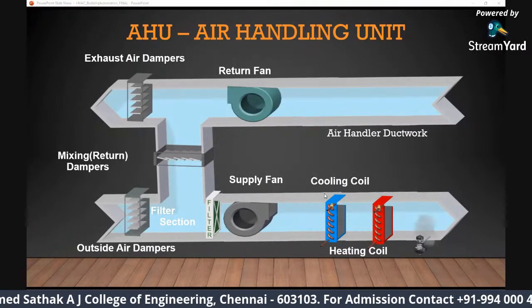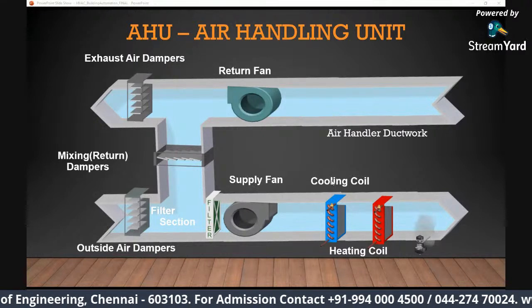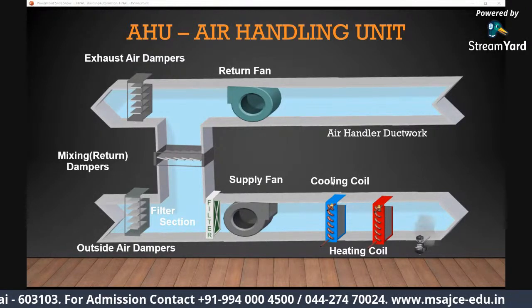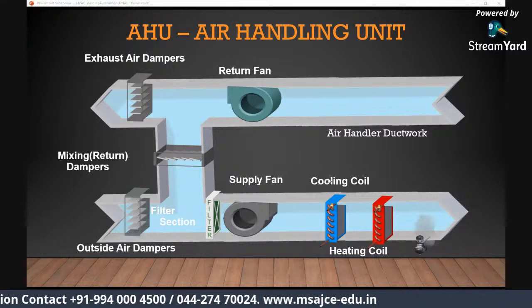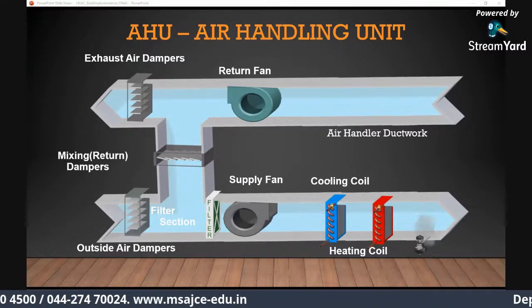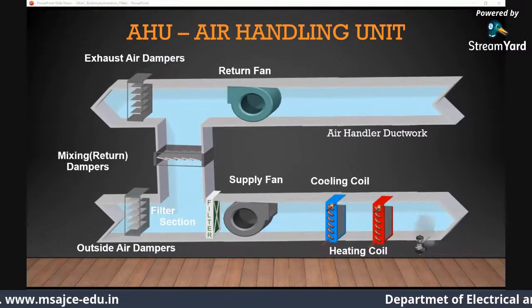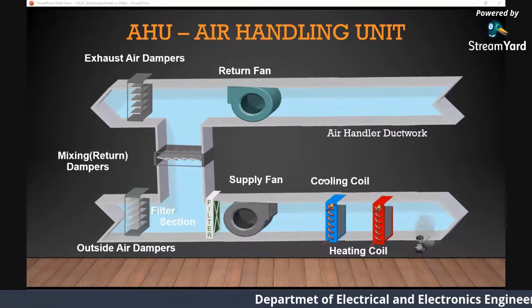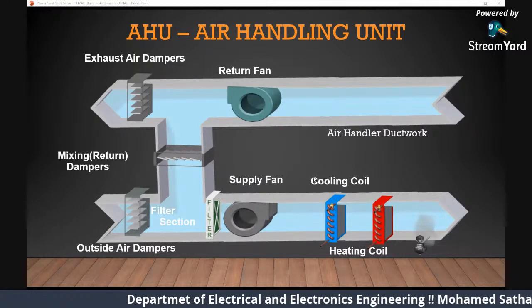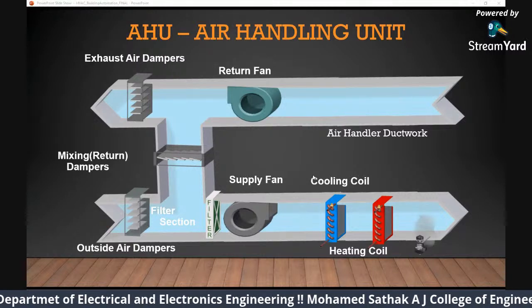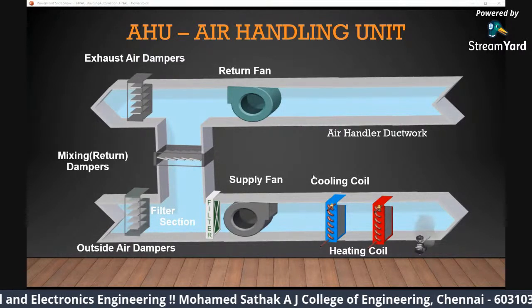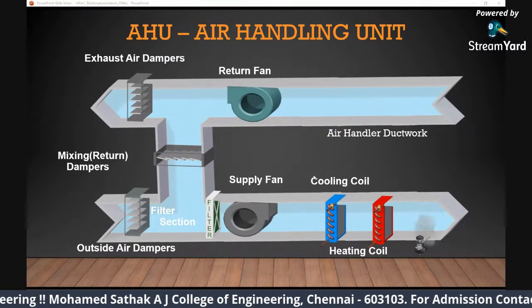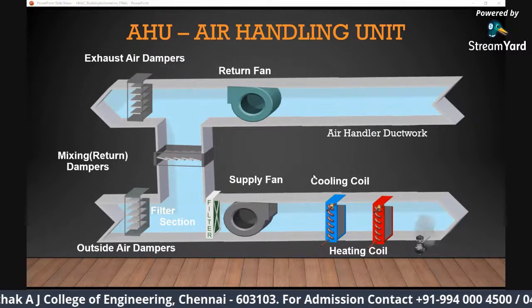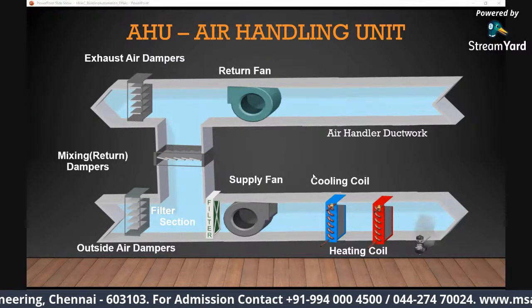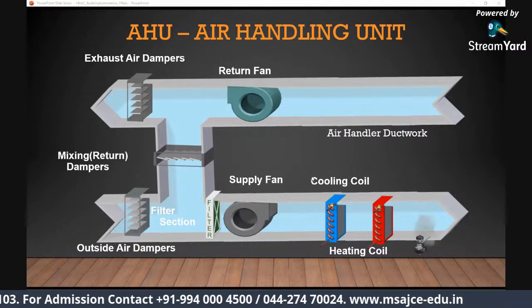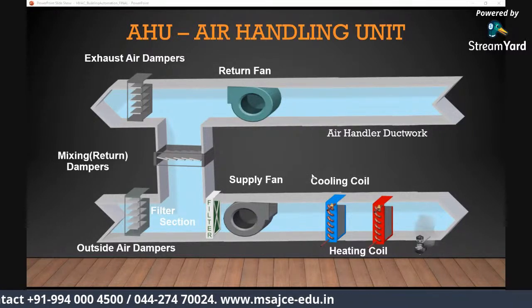So this is your typical or ideal graphical representation of an air handling unit. This is not how it looks. I'll show you in the next slide how an AHU looks, but this is how we show in the front end or an HMI, like a SCADA or something like that, how the AHU operates. Again, as I mentioned, the typical purpose of an AHU is to supply air to a building. You need airflow, right? So the major component of an AHU is a fan. You need a fan to pump in air from outside or to rotate the air inside the building. As I said, you can compare an AHU to a ceiling fan. The only purpose is to serve air to the building or to the closed space.